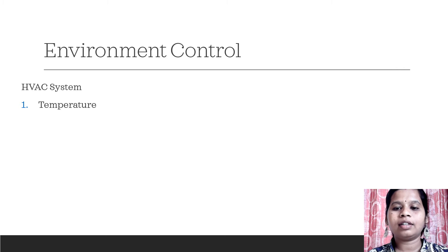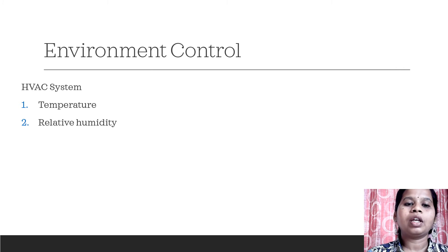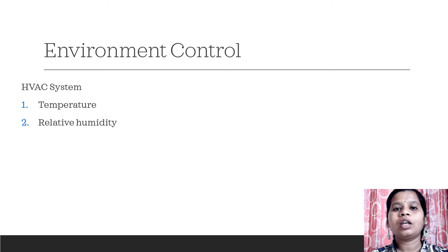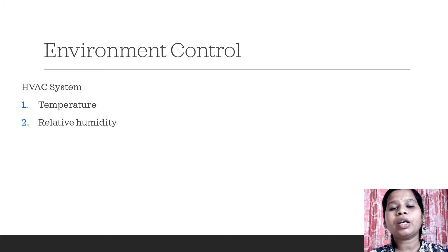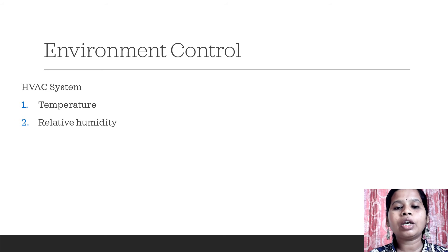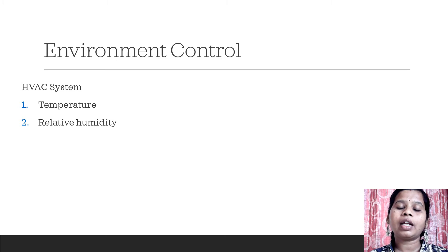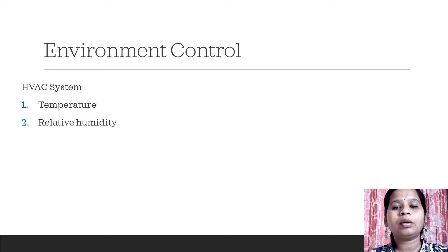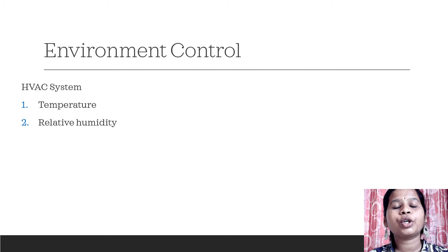Depending on specific requirements, the temperature can be less than 23 degrees Celsius. The next factor is relative humidity, which is also product dependent. Normally a relative humidity of 45% plus or minus 5% is maintained. If we are having dry powder filling, it can be reduced to 30% plus or minus 5%, and if we are handling moisture-sensitive products, it can be reduced further to 20%.